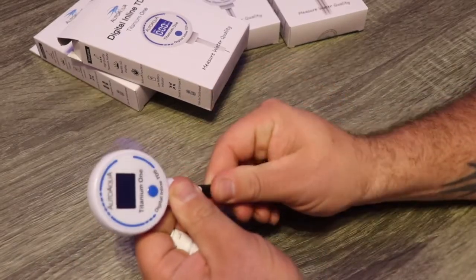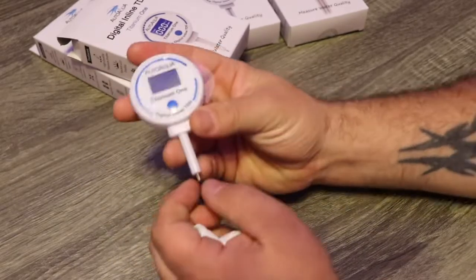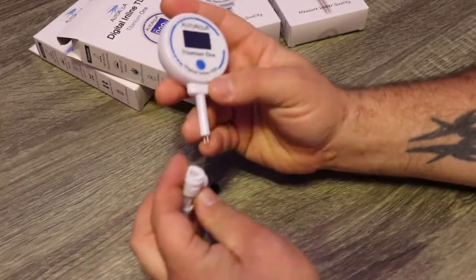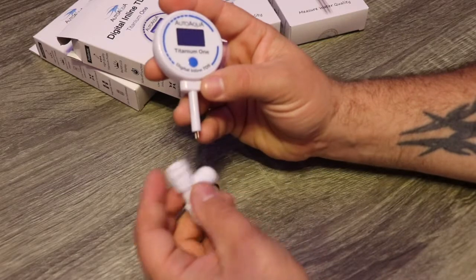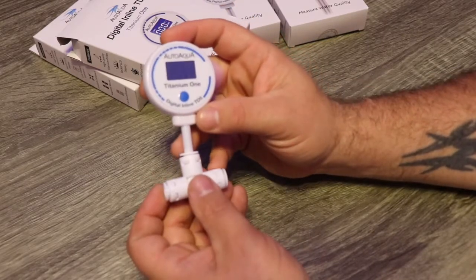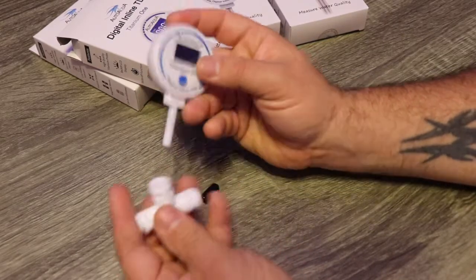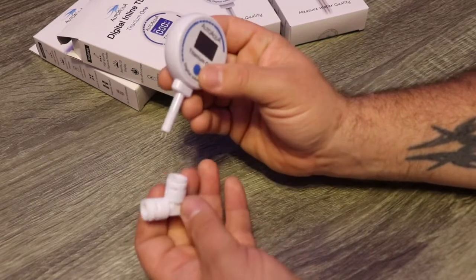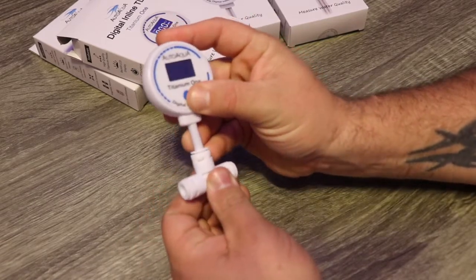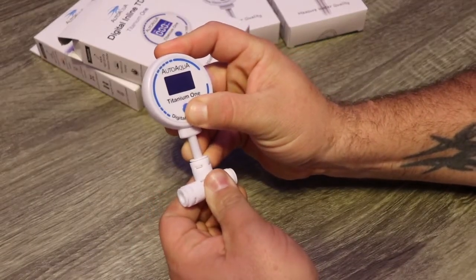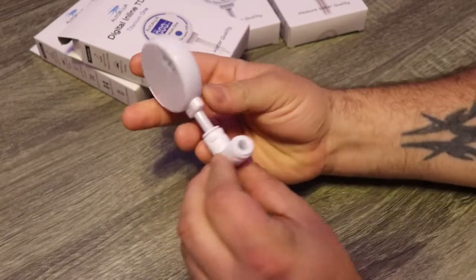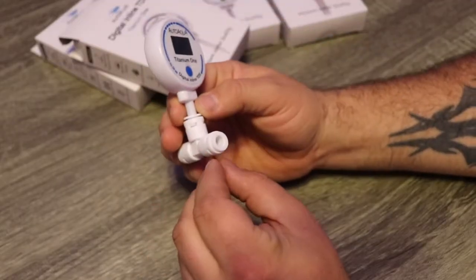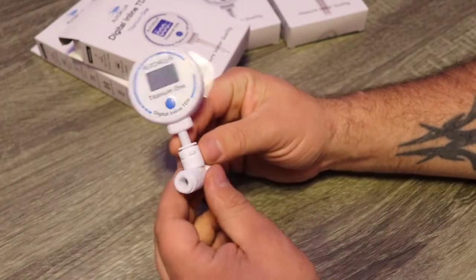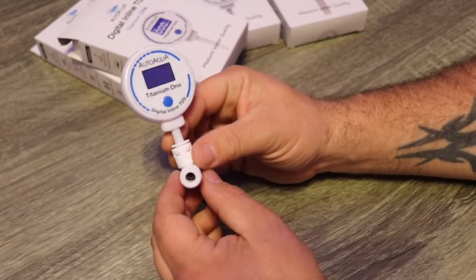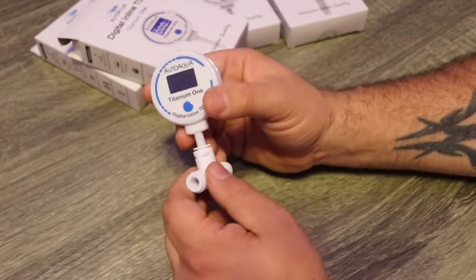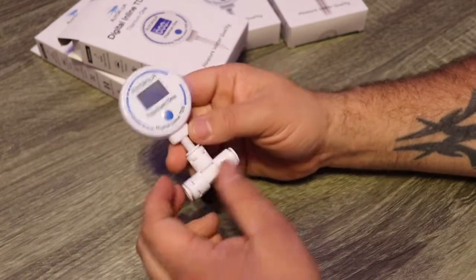Essentially you have this quick connect device here. You remove this plastic piece, which is protecting the probes inside, and you can do this a number of different ways. You can put it in like this, or like this, depending on what your situation requires. But when you put it in, you want to make sure that you're not damaging those probes, and essentially have it so that both probes come in contact with the water passing through this quick connect. Now, this is the titanium one.